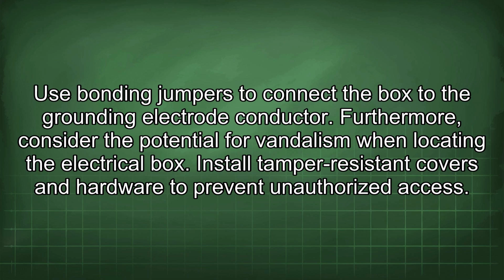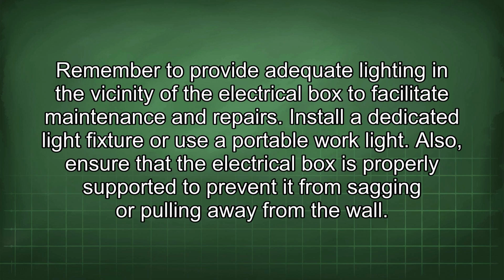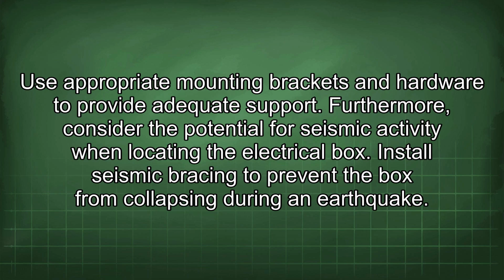Furthermore, consider the potential for vandalism when locating the electrical box. Install tamper-resistant covers and hardware to prevent unauthorized access. Remember to provide adequate lighting in the vicinity of the electrical box to facilitate maintenance and repairs. Install a dedicated light fixture or use a portable work light. Also, ensure that the electrical box is properly supported to prevent it from sagging or pulling away from the wall. Use appropriate mounting brackets and hardware to provide adequate support.